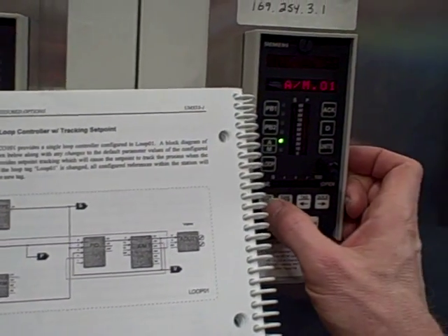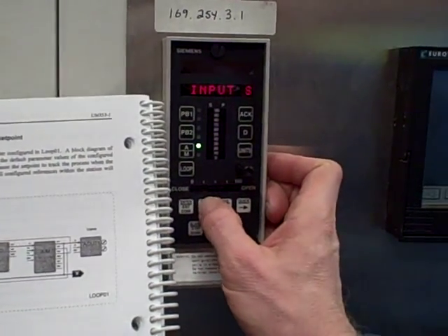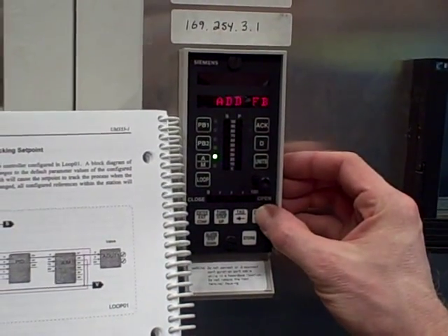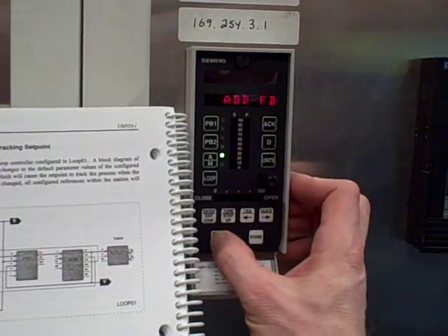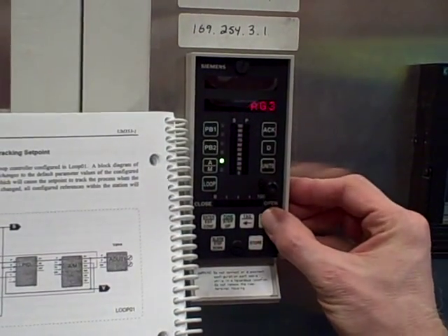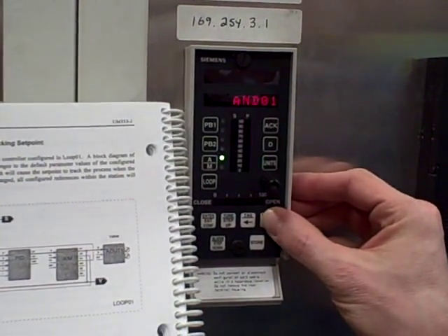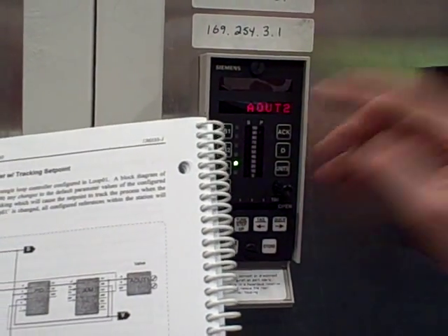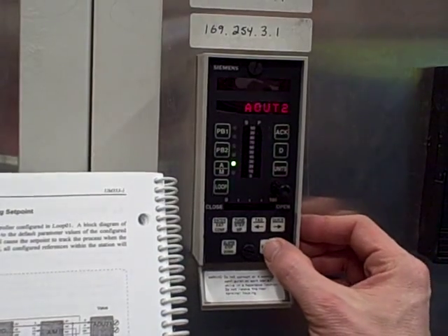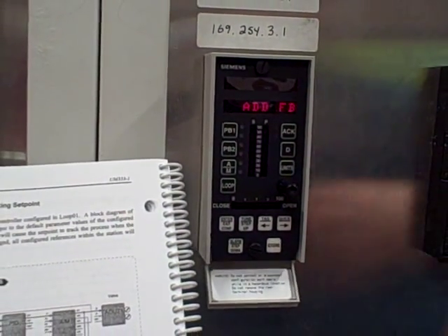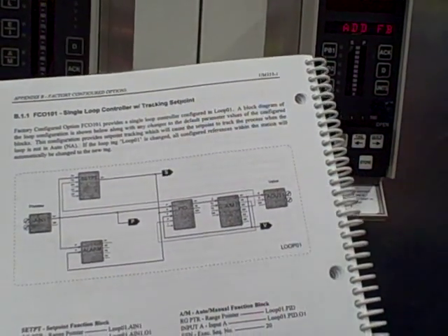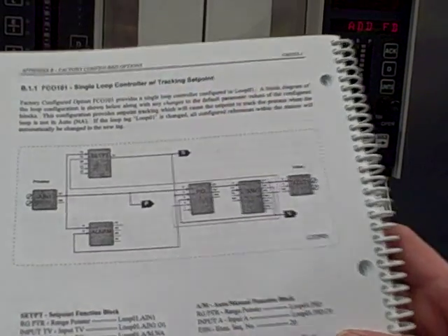Now I'm going to step up and go to 'add a function block' instead of 'edit function block.' Stepping down, it shows all the possible function blocks that aren't being used, and one of those is analog output number 2 right there. I want to store that. Now I've just added another function block to my program. However, that function block is just floating around — it's not connected to anything. We need to connect it.